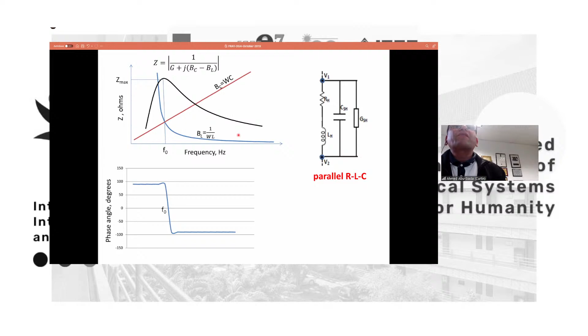So what do we expect if we have a very complicated circuit? I showed you only one disk, the equivalent circuit of one disk. If we have multiple disks like this, with multiple series and parallel branches, we expect multiple resonance and anti-resonance points. And that's what you will get in practice. You will get a signature like this. The x-axis here represents the frequency from, as you can see, 10 hertz to 2 megahertz. The y-axis here could be impedance, could be admittance, or could be transfer function, as in here in dB. And what you are seeing here are the frequency responses of the three phases, phase A, phase B, phase C.